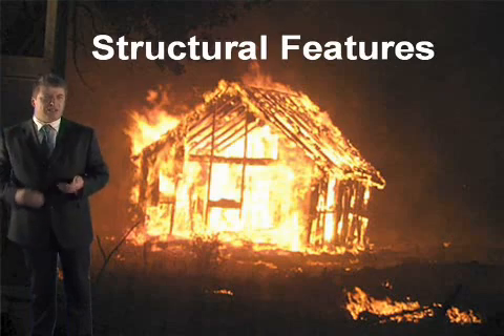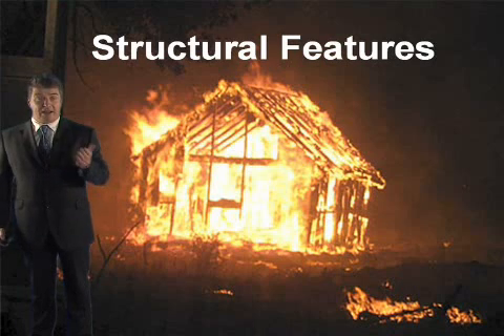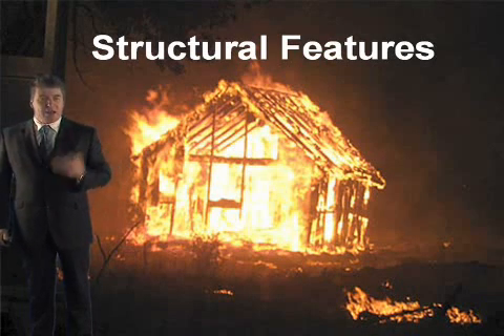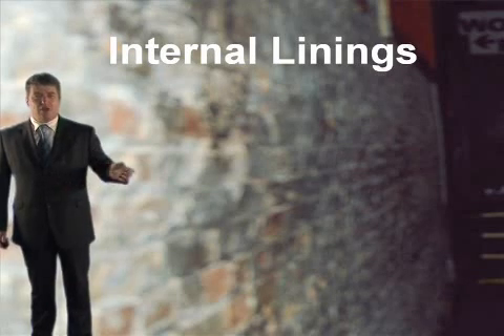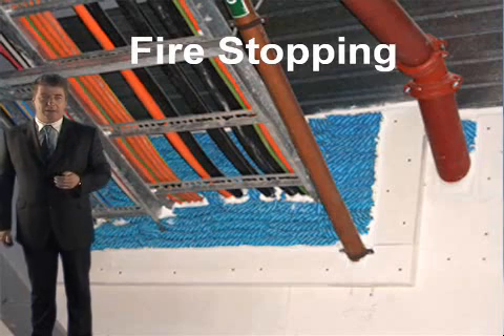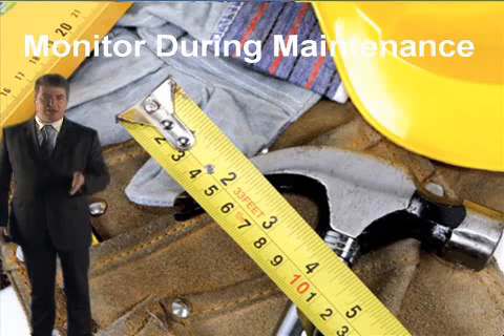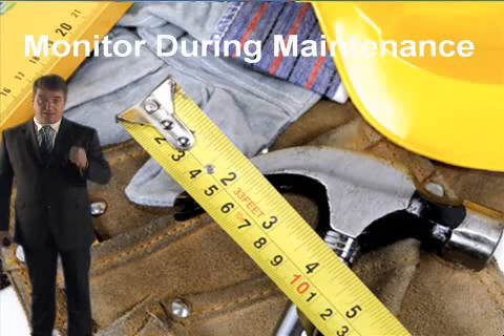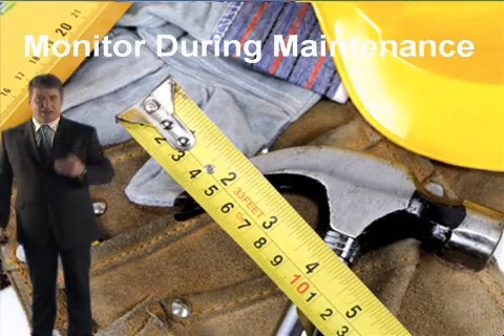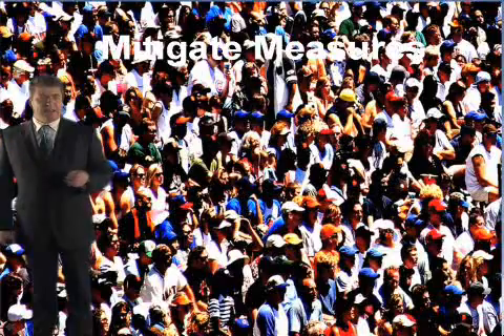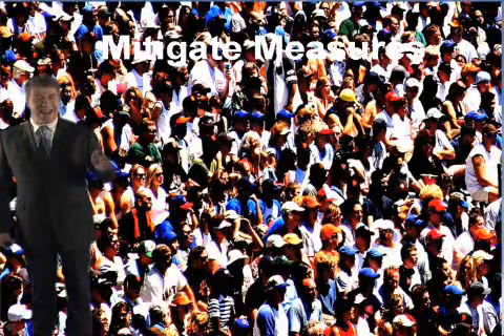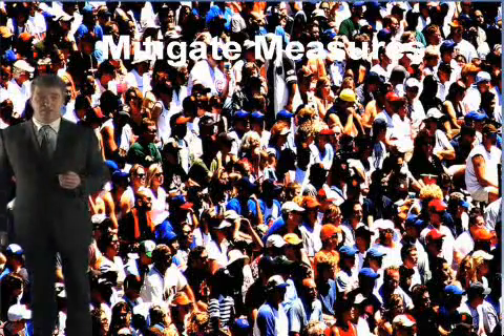You've also got to consider structural features that could promote fire spread. For example, cavities in the building, open stairways. You've got internal linings. You've got issues with inadequate fire stopping. You've got to make sure it's been monitored during maintenance and refurb, because obviously when you do maintenance and refurb, that's when your risk changes. And you've got to mitigate measures in place for persons in and around. Don't forget relevant persons, anyone in the immediate vicinity of your building.